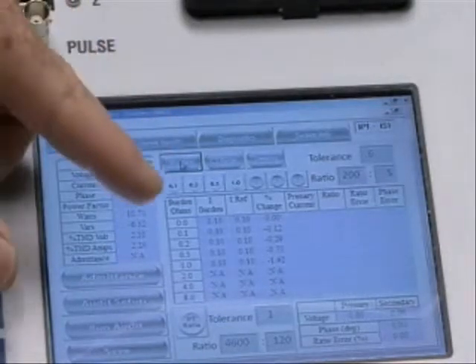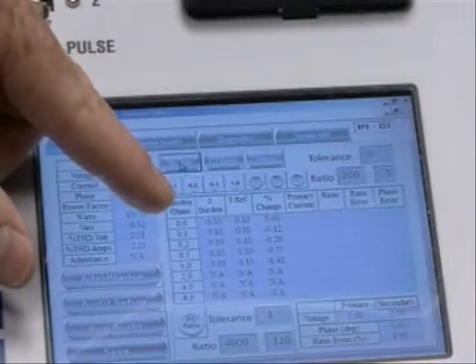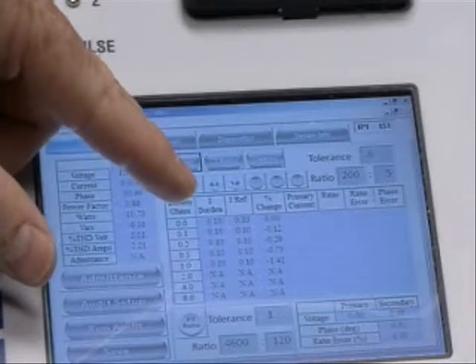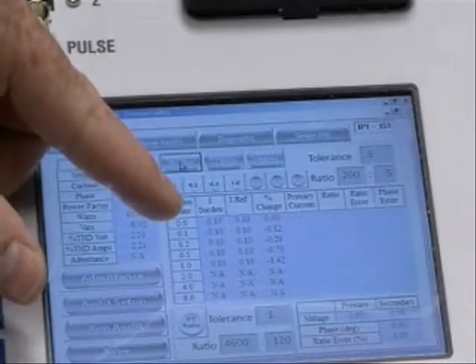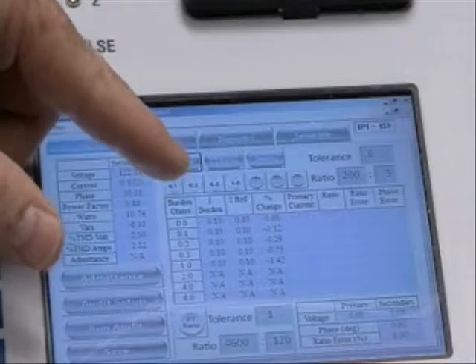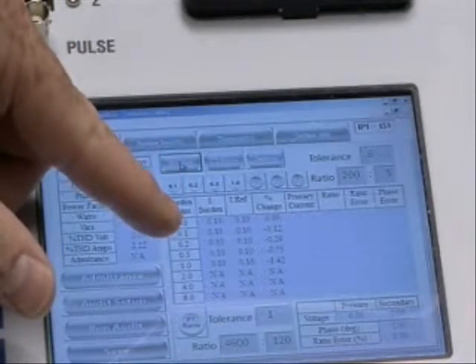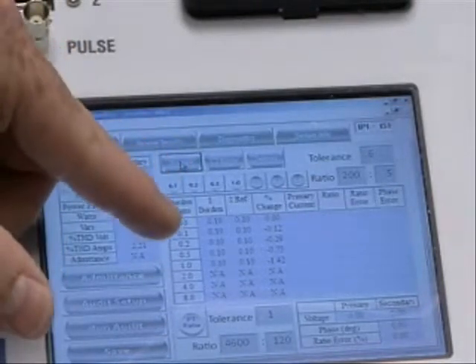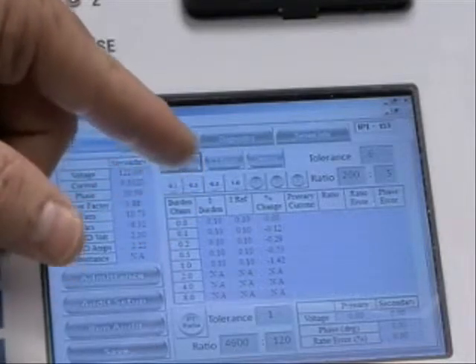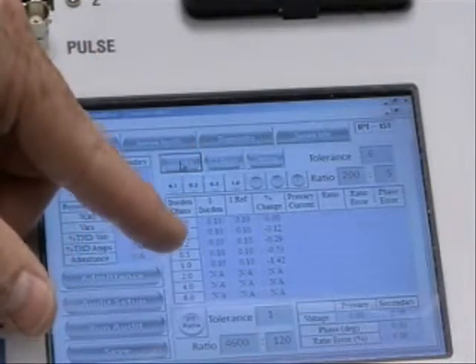So the TX Auditor reports back our measurement of current at 0 ohms being 0.1 amps. And our 0.1 ohm burden test gives us 0.1 amps. And our 0.2 ohm burden test gives us 0.1 amps. And our 0.5 ohm burden test gives us 0.1 amps. And then again at 1.0.